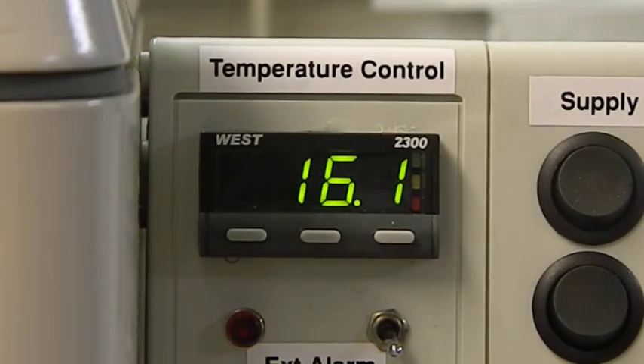If all those parameters are correct in the machine, then the machine will operate at standard factory settings. Just beware that you haven't got any minus figures in front of numbers where there shouldn't be minus figures. Check also that if you've altered the tune parameter to easy, it will reset all the second set of figures, and they will not come back. You'll have to input them again in the manual mode.